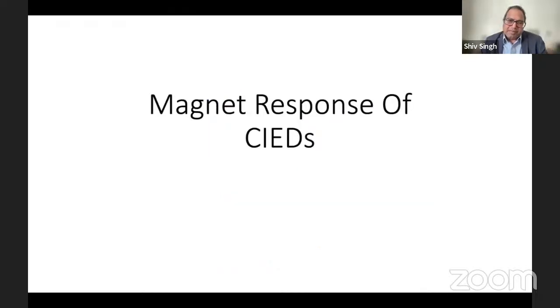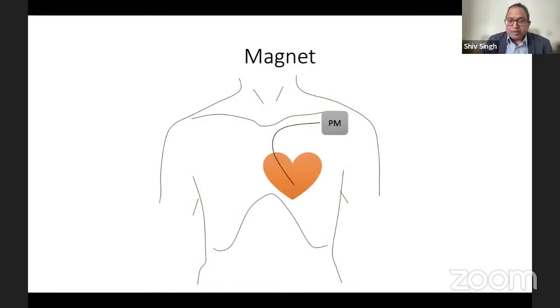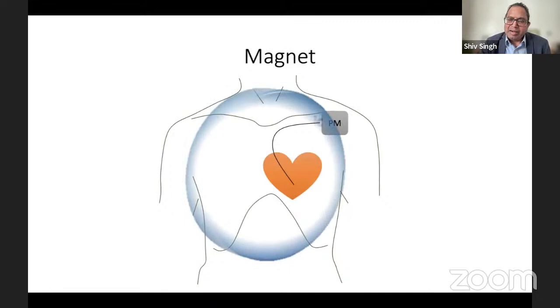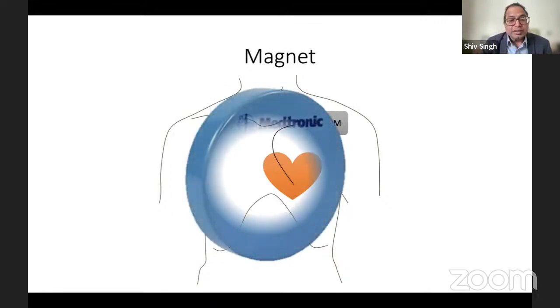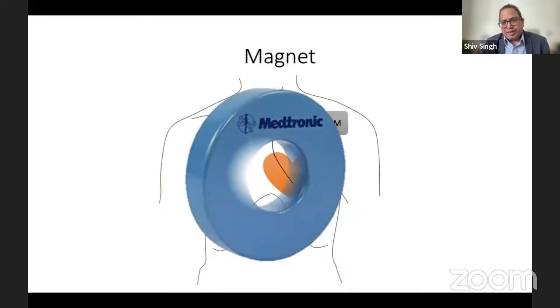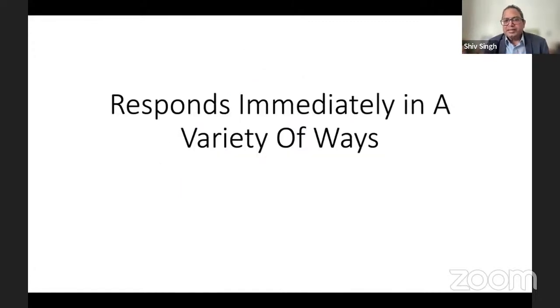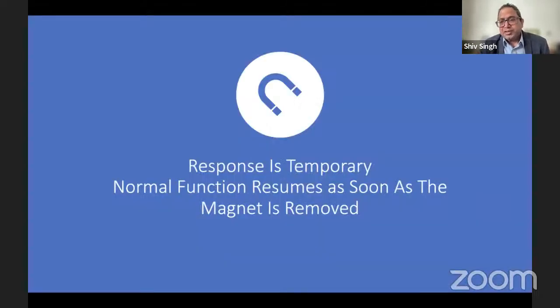So next one is about magnets, and this is an important topic. What do magnets do to pacemakers and ICDs? If you place a magnet over a pacing unit, what would happen? That's the magnet we use in our setup. A pacemaker will respond immediately when you put the magnet on, but the response is temporary. As soon as you take away the magnet, it resumes its normal setting.